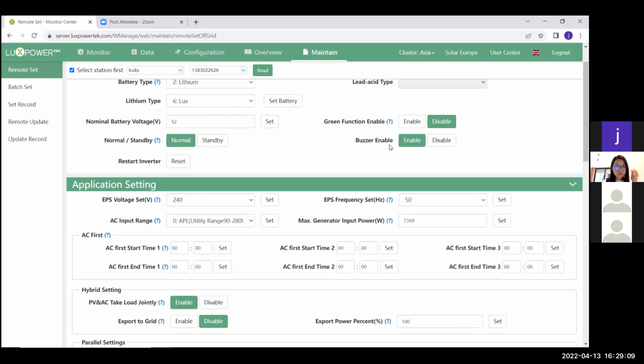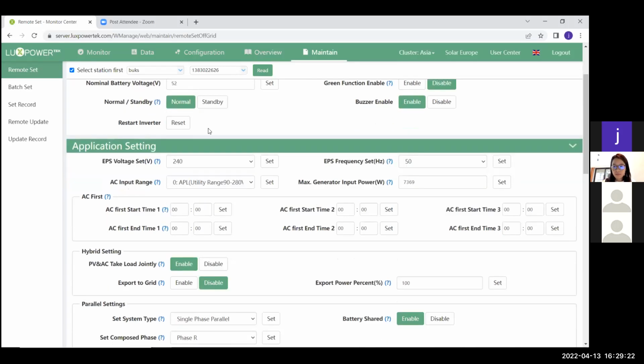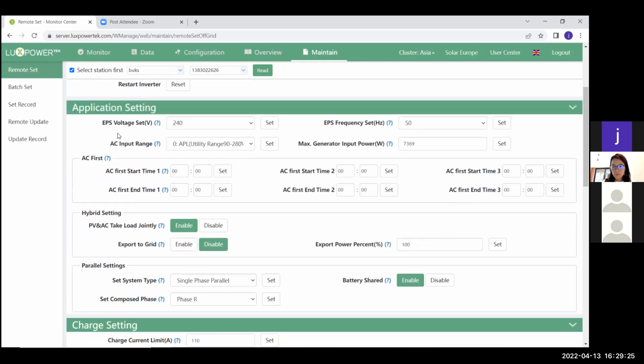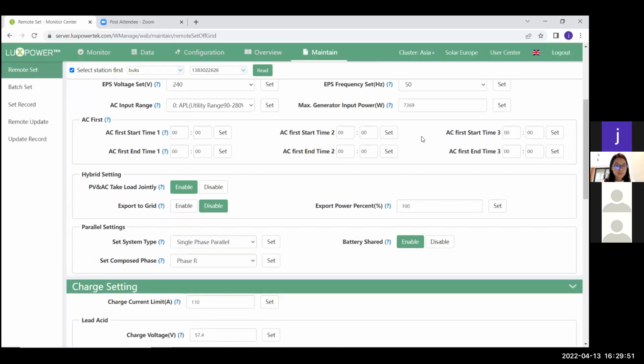Then this buzzer is just the buzzer sound that you hear when you press the settings and so forth. You can decide if you want to disable or enable that buzzer. Restart inverter is only if you want to restart your inverter remotely. From here on is your EPS voltage setting. You can set this voltage to 230. This client wanted it at 240, so he set it at 240. This is the voltage that your inverter will relay from the EPS side, so your AC output will be the voltage that you set here. Then EPS frequency, 50 Hertz, which is what we use here in South Africa. Then max generator input in watts.